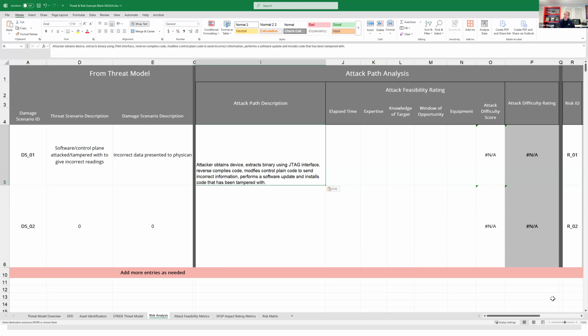Assume that you don't when you're doing the threat and risk assessment would be our recommendation, because then it's going to be a very complete threat and risk assessment. It's going to lead to the documentation of the fact that you put in the software update, given a specific sort of threat and risk, and it's just going to flow right into your documentation, and then it's going to check the box or address the issue that the FDA has, which already you're going to need secure software updates for your medical devices. Yeah.